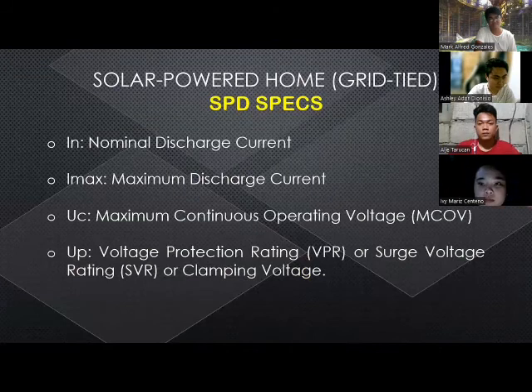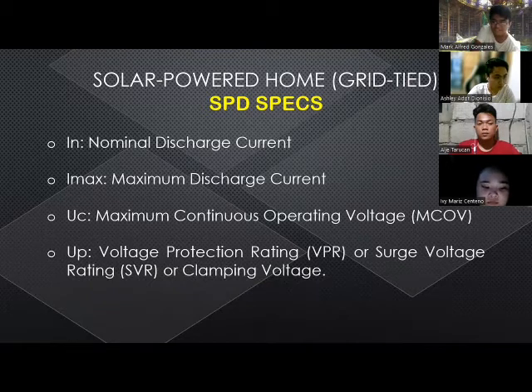SPD specs include nominal discharge current, maximum discharge current, and UC, maximum continuous operating voltage or MCOV, and voltage protection rating VPR, or surge voltage rating or clamping voltage.